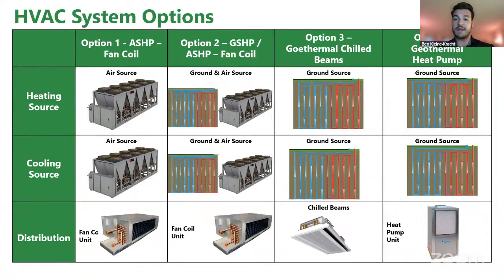For the chilled beams though, that's a little more in depth. We would probably look to a small modular air handler for that kind of space. With the chilled beam options, it's a 4-pipe system, so we have hot water and chilled water available. We would probably use a small modular air handler to serve the bigger spaces, utilizing the chilled and hot water already in the building at the air handling coils - that's probably how we would do that.